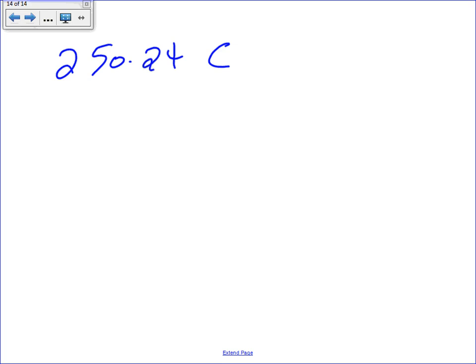It says the grounded conductor shall not be smaller than the required grounding electrode conductor. So we're doomed. If you continue, if it's more than 1100 kcm, then it's not less than 12.5% of the area of the largest ungrounded conductor. Based on this rule, the whole mess happening here is because we are paralleling.